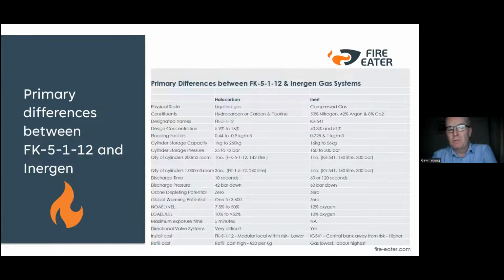The storage pressure for the cylinders is between 25 and 42 bar. With Inergen, it's between 150 and 300 bar. So that means basically that your Novec cylinders need to be within 10 meters of your computer room or within the computer room, whereas Inergen systems can be located 100 to 200 meters away from the risk, in the basement of a building, for example.